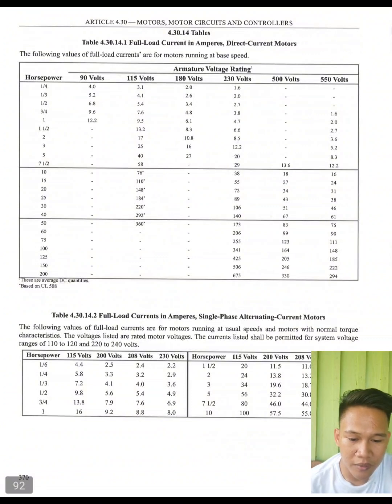So next is we have the table 4.30.14.2, full load current in amperes, single phase alternating current motors. So, the following values of full load currents are for motors running at usual speeds and motors with normal torque characteristics. The voltages listed are rated motor voltages. The current listed shall be permitted for system voltage ranges of 110 to 120 and 220 to 240 volts.